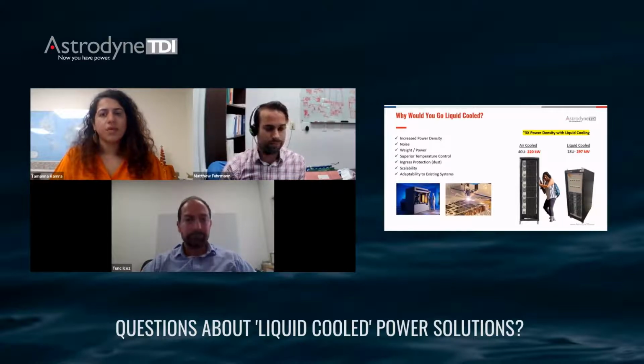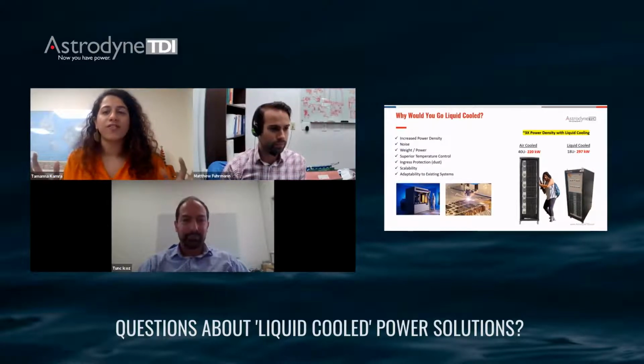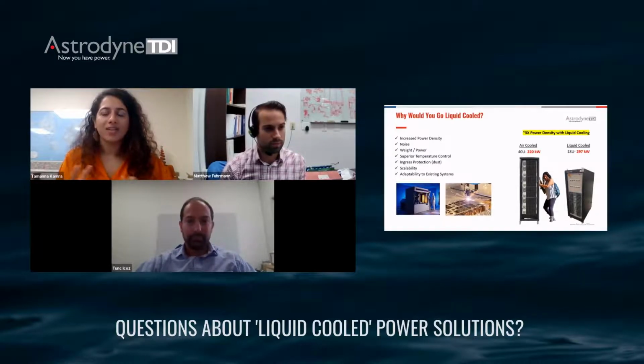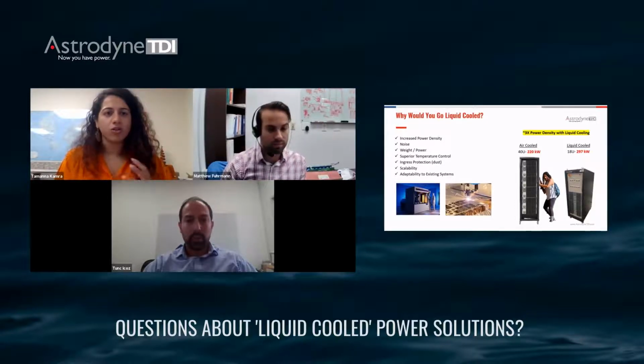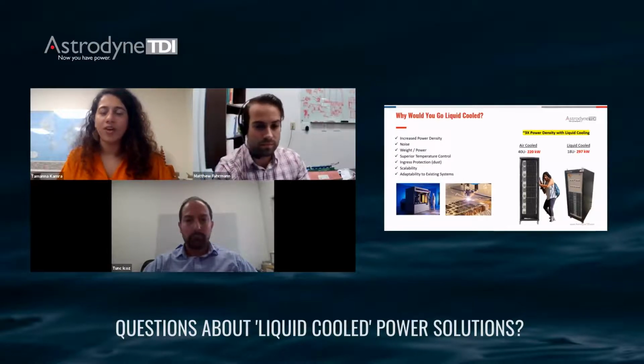So it sounds like the two big factors here are power density - you can see on the pictures on the right, you get almost 3 times the power density with liquid cooling in the same amount of space. You can see me trying to climb the air-cooled cabinet - it's rather big, and the liquid-cooled cabinet, which is smaller, actually delivers more power. The second thing is the environment - you can work in an ultra dirty or ultra clean environment with liquid cooling. So a lot of great benefits here.